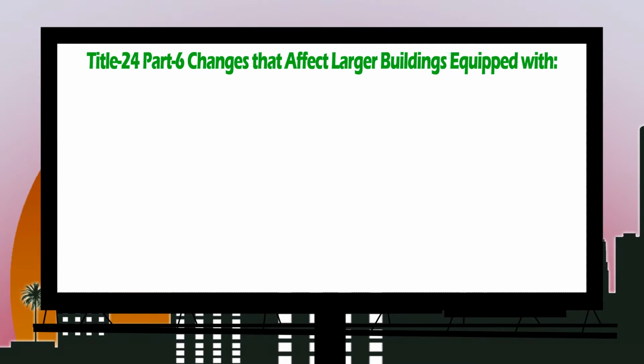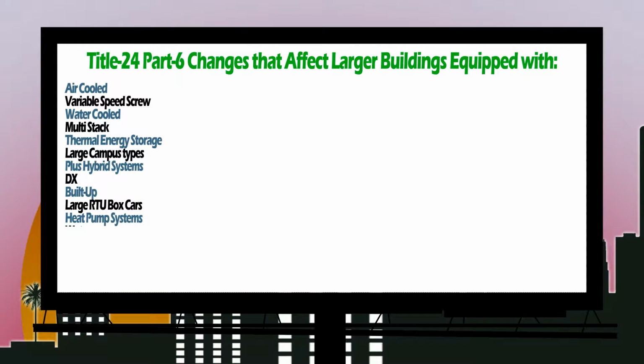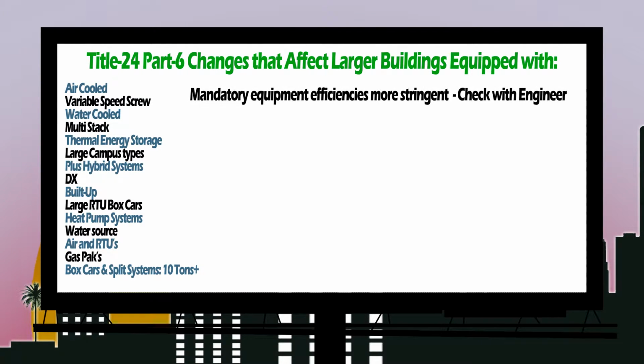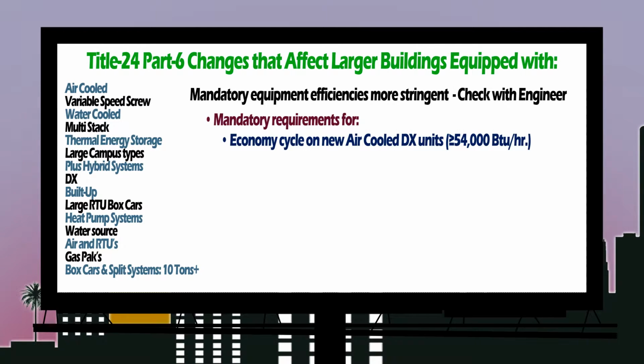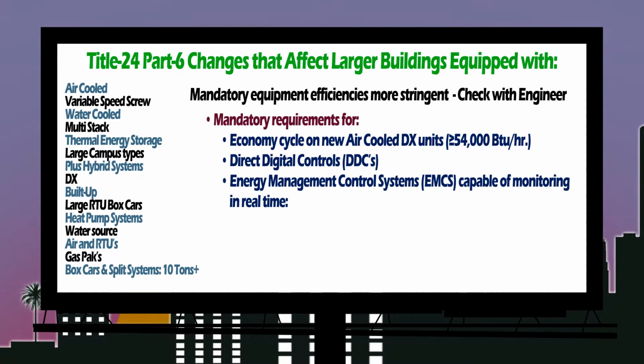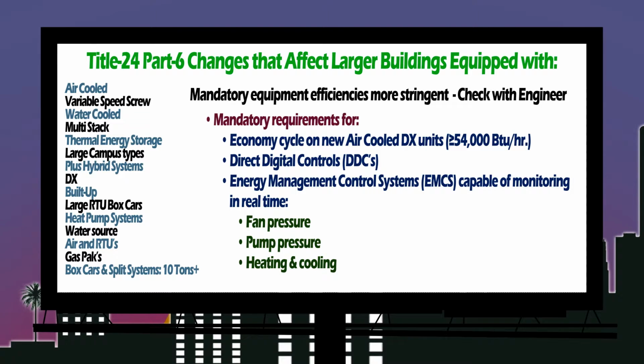To wrap up, let's review a few additional mechanical notes for HVAC Title 24 Part 6 changes that affect larger buildings equipped with various chillers, such as the examples listed here. First, mandatory equipment efficiencies are more stringent. Check with your engineer to ensure compliance. Next, there are mandatory requirements for an economy cycle on new air-cooled DX units of 54,000 BTUs an hour or greater. And direct digital controls, or DDCs, and energy management control systems, EMCS, capable of monitoring several points such as fan pressure, pump pressure, heating and cooling, etc. in real time are mandatory.